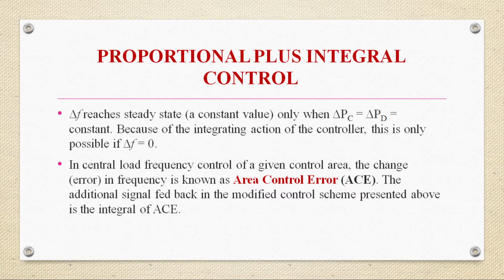So the steady state change in frequency has been reduced to 0 by the addition of the integral controller. Delta F reaches a steady state value, that is a constant value, only when delta Pc is equal to delta Pd, which is equal to a constant. Because of the integrating action of the controller, this is only possible if delta F is equal to 0.